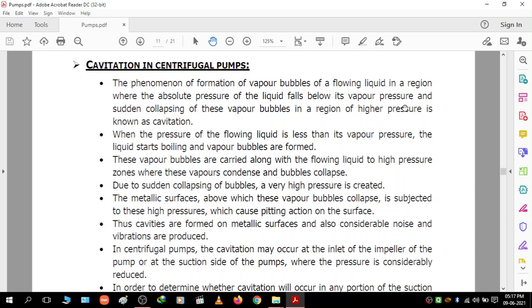The sudden collapsing of these vapor bubbles in a region of higher pressure is known as cavitation. These bubbles are carried along with the flowing liquid to high pressure zones where the vapors are condensed and bubbles collapse suddenly. Due to sudden collapsing of bubbles, very high pressure is created. The metallic surface on which these vapor bubbles collapse is subjected to these high pressures causing pitting action. Thus cavities are formed on metallic surfaces and unbearable noise and vibrations are produced, leading to efficiency loss.